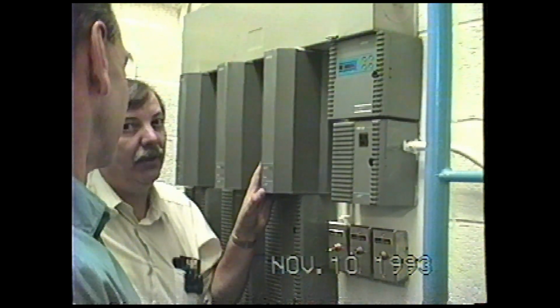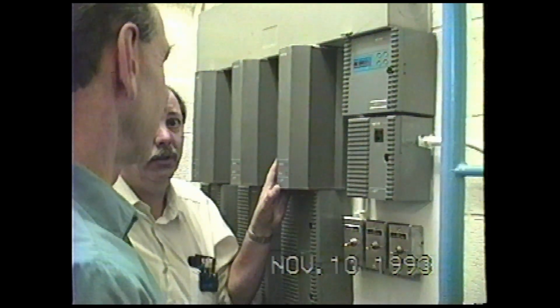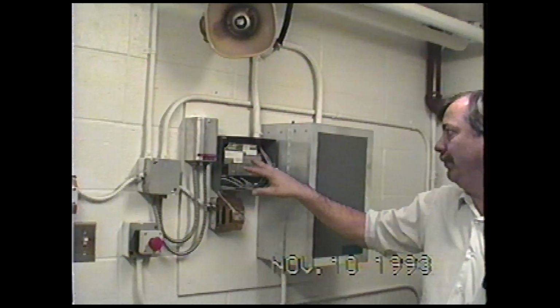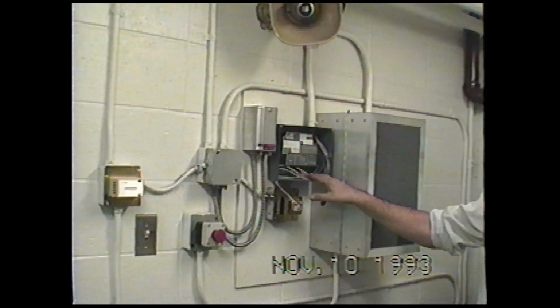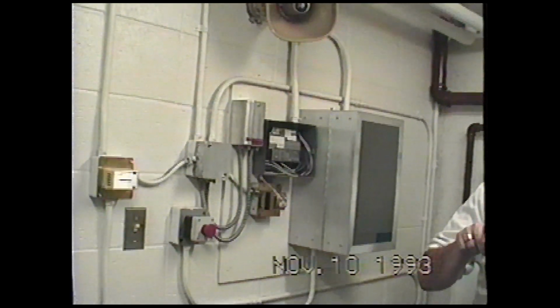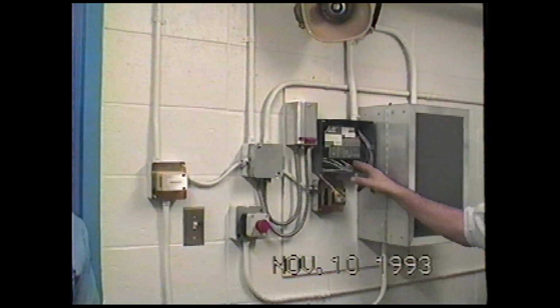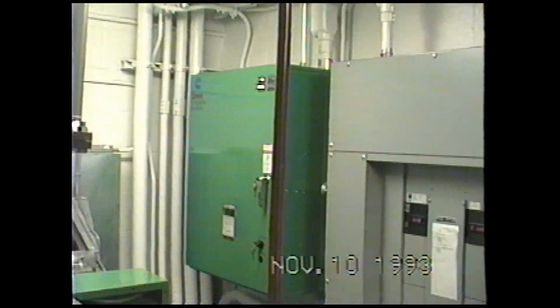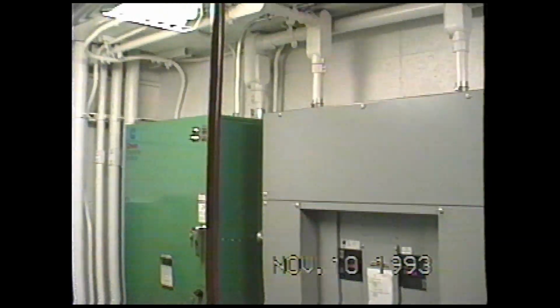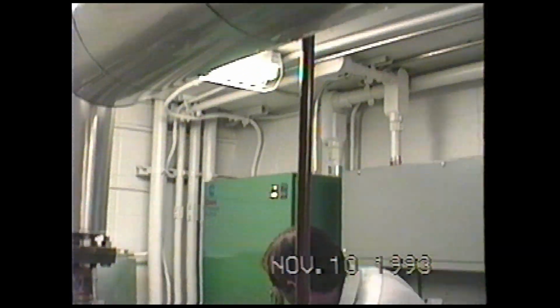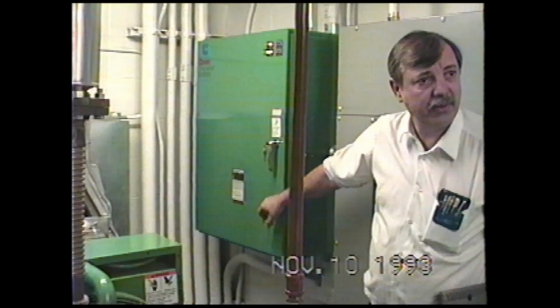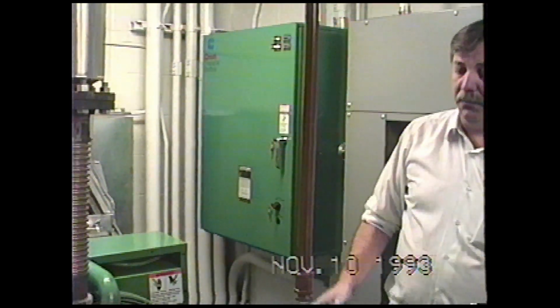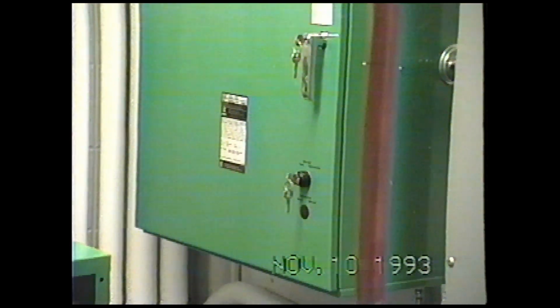No, that would mean 5 years continuing to be off. It's like a wireless backup. These have a program storage controller in it. It's just a general input-output device, but its whole reason in life is to start up the emergency generator for load shedding only. There's a relay inside the generator panel that energizes early, and that relay is wired across this retransfer switch. It's the same as someone turning the switch, and boom, the generator starts up and runs.